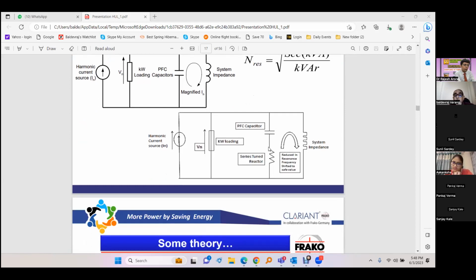One is that a reactor will dampen the inrush current. It will reduce that. Secondly, it will shift the resonance point to a safe place. Suppose the resonance was taking place at the 7th frequency or the 5th frequency, it will come down and be between the 3rd and 4th, or maybe the 2nd and 3rd, where there is no harmonic. So it is a safe place. So the resonance is avoided, and the inrush current is reduced.